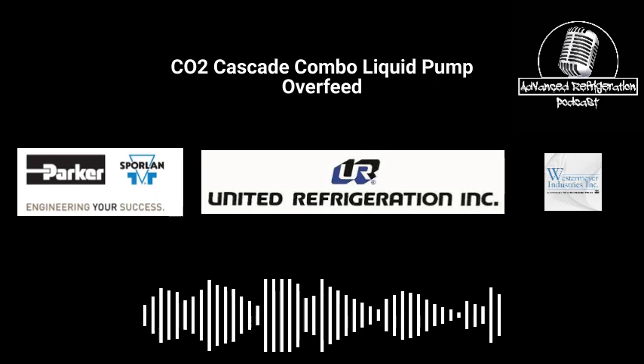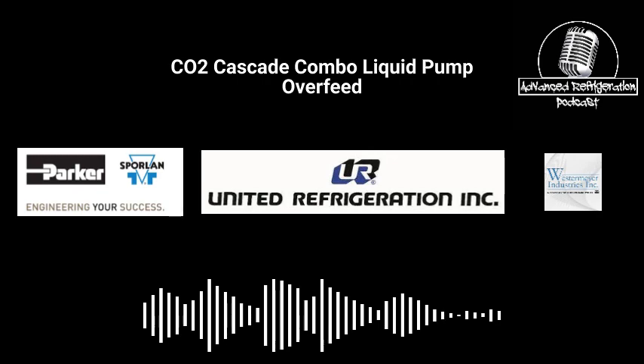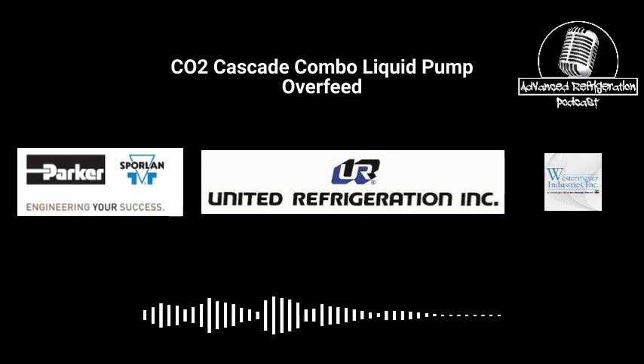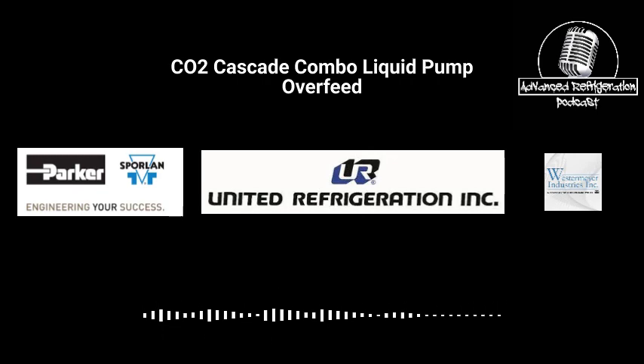The other different thing on this, the ones that I've seen have been controlled by CPC, and usually with any kind of CO2 rack, whether it be regular cascade or liquid pump overfeed, when it comes back on, the cases are staged within times via the control program. This one Hill Phoenix rack that I'm speaking of does not. They turn on all the cases at the same time with one relay. They utilize the shutdown for the rack, with all the multi-outs connected to all the enables from the phase loss. So if something happens to the rack, it just shuts down all the cases.